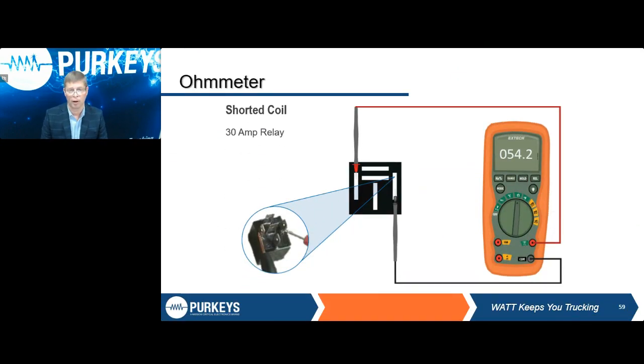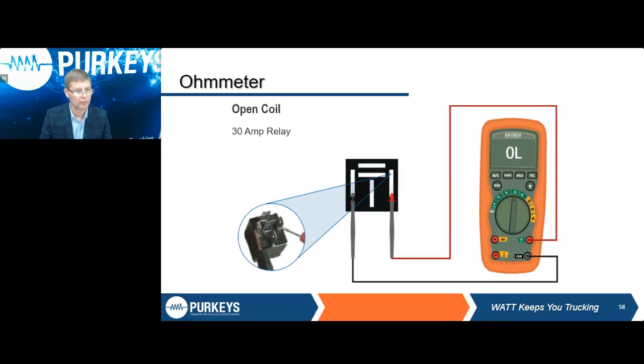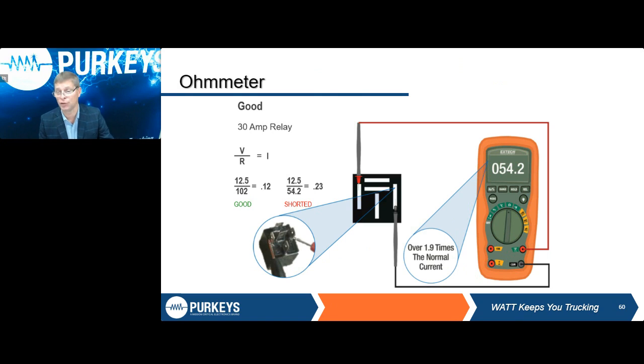We're going to grab this one, go across it with our ohmmeter. This one only has a resistance of 54.2. Does it work? Technically, yes. You can hear it click, it's doing its job. But if we do the calculations like we did before, oops, bear with me. We still use the 12.5 volts, but now we're going to divide it by the 54.2. Now look what that did to our current draw on that relay. It went from 0.12 amps to 0.23, almost doubled it.